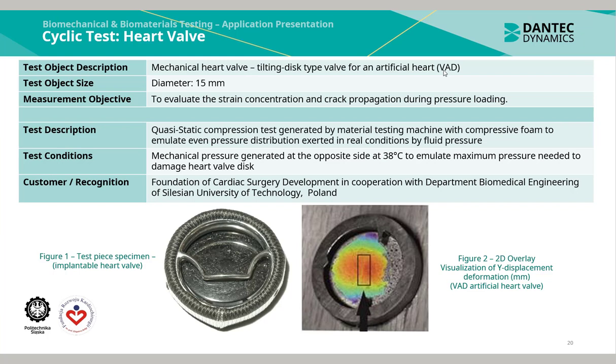Quasi-static compression tests generated by material testing machines with compressive foam are used to emulate even pressure distribution exerted in real conditions by fluid pressure on the valve. On the left we see the test piece specimen of the implantable heart valve and on the right we see a 2D overlay of the Y-displacement deformation of the VAD artificial heart valve.